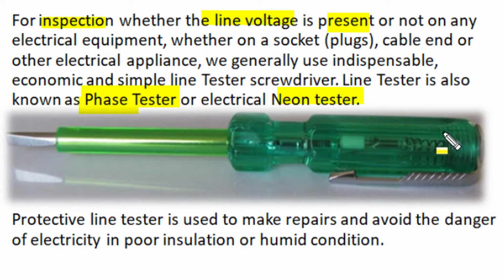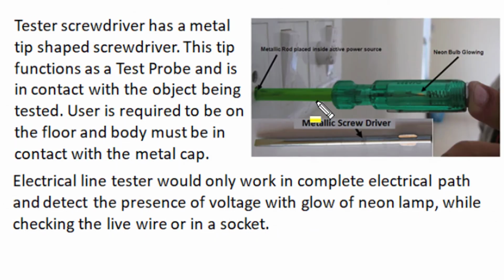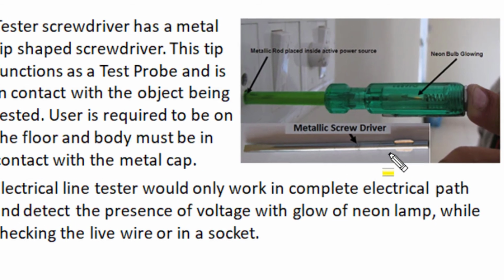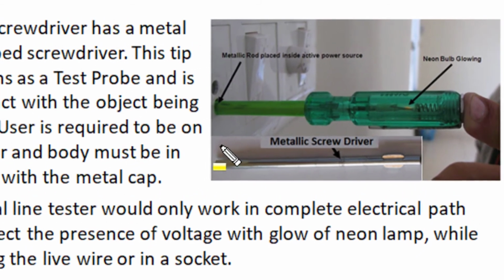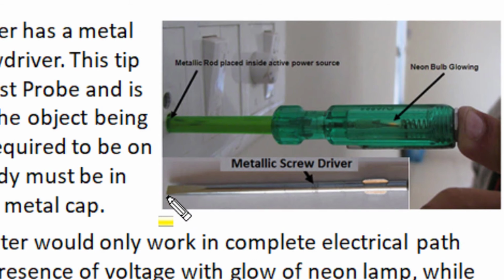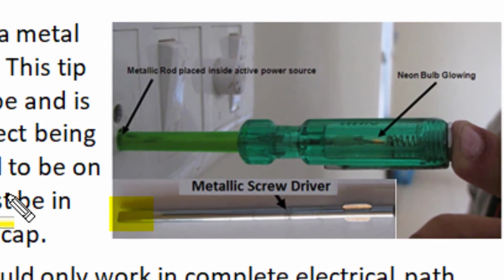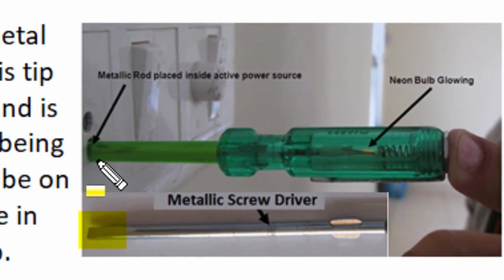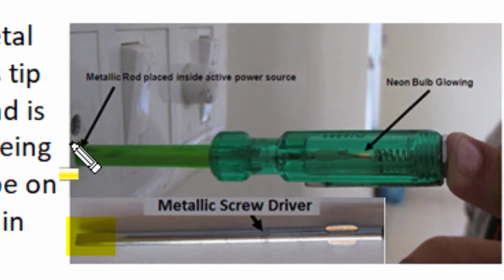We use such a protective line tester to make repairs and for fault finding, and when we use it, it safeguards us and avoids the danger of electricity, whether there is poor insulation or humid, wet conditions surrounding our electric installations. One free end of this line tester is a metallic rod, and the metal tip of this rod is given a screwdriver shape. This tip acts as a test probe and is placed in contact with the object that we have to test.